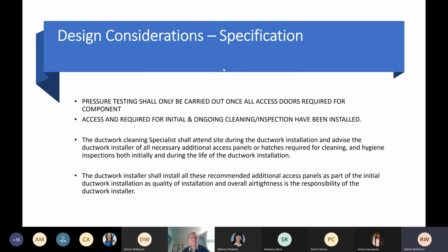Here, this is an extraction from another specification where they're actually saying the ductwork cleaning specialist shall attend site during the ductwork installation and advise the ductwork installer of all necessary access panels or hatches required for cleaning and hygiene inspections, both initially and during the life of the ductwork installation.